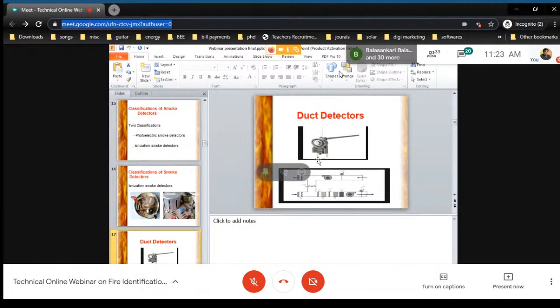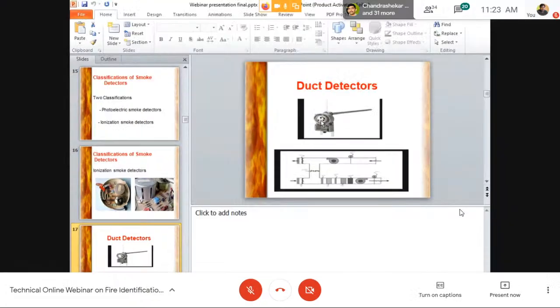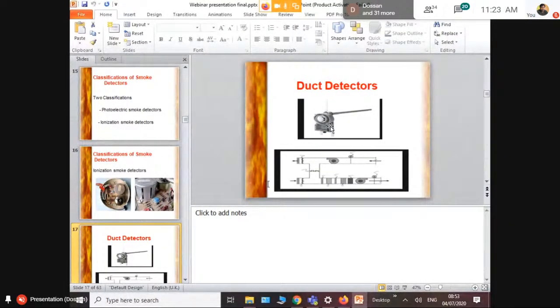The next type of detector we are going to see here is the duct detector. This is how it is. To be more clear, this is the smoke detector which you are seeing here. The duct detector is nothing but a smoke detector installed with a sampling tube. The sampling tube will be punched inside a duct. Now, going one step back, what is a duct? A duct is something which supplies airflow to the areas. I have given a small pictogram of how it works.